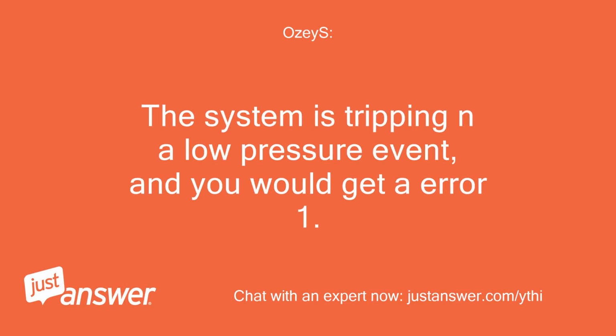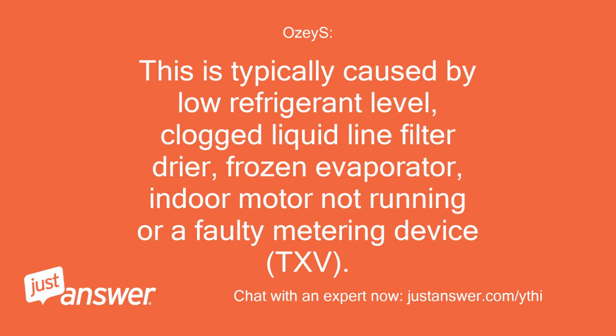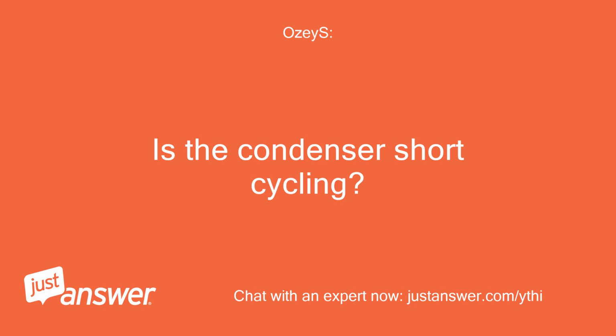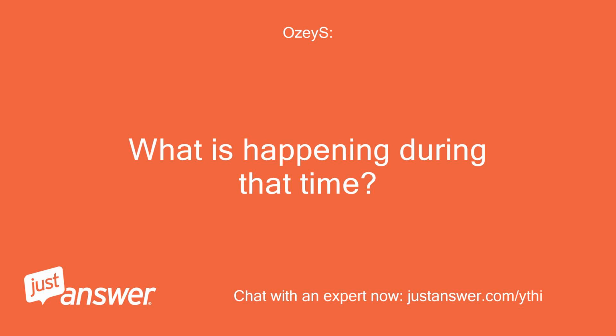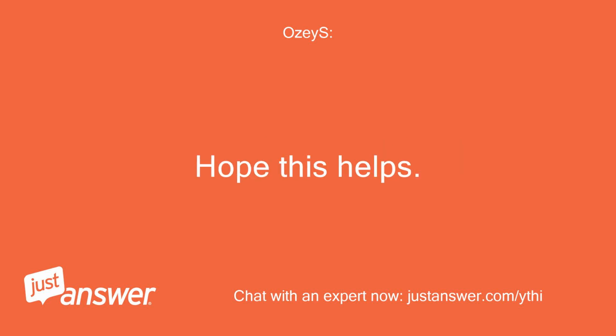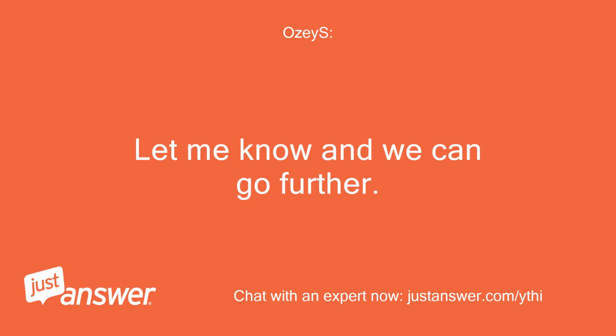The system is tripping at a low pressure event, and you would get an error 1. This is typically caused by low refrigerant level, clogged liquid line filter dryer, frozen evaporator, indoor motor not running, or a faulty metering device, TXV. Is the condenser short cycling? What is happening during that time? Hope this helps. Let me know and we can go further.